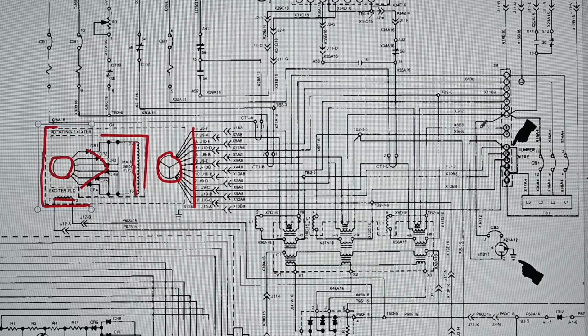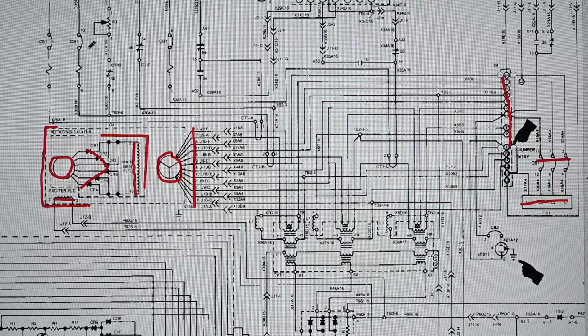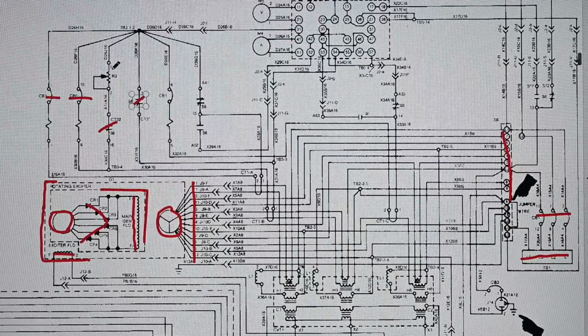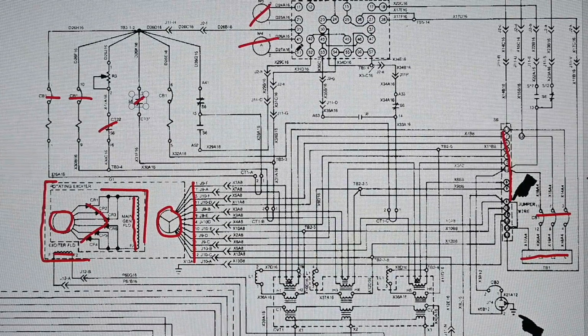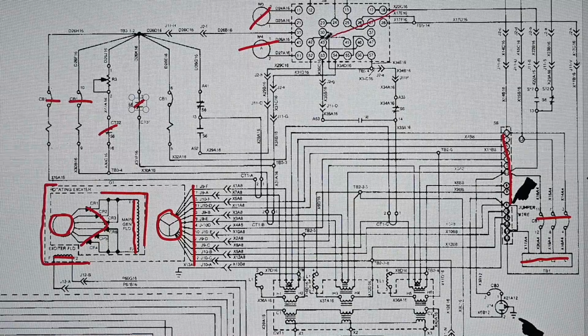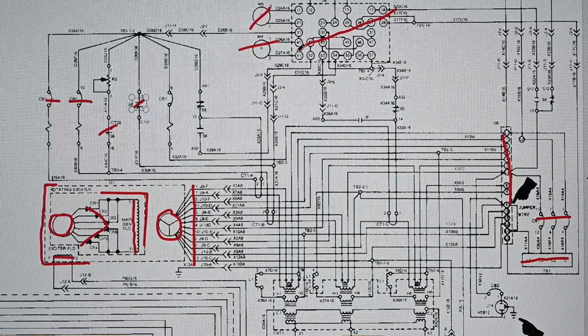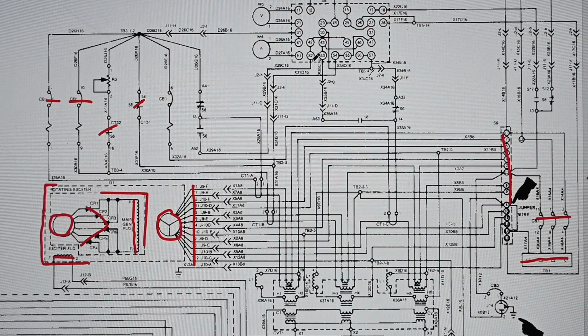And those 12 wires are ultimately reconfigured in this switch over here, and then the main output terminals right there. So there's 4 main output terminals, and you use different terminals depending on how the generator is configured. 3-phase ends up using all 4 terminals, and for 120 volt single phase, only 2 of the terminals are used, so just different configurations. Main circuit breaker across right here, and you can see there's some more auxiliary contacts up here that are part of the circuit breaker, and up here and up here. Instrumentation, voltmeter, amp meter up here. This main switch across here is for selecting the different phases that you want to monitor the voltage and current on. So let's take a look at the voltage regulation circuitry.